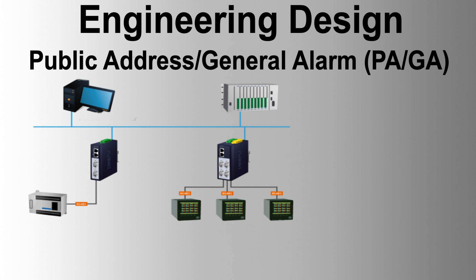System spare capacity and spares: 20% spare capacity on interface I/O cards, wired and terminated. 15% spares for cards, terminations, and slots available but not installed. 25% expansion space in cabinet racks. 30% maximum system memory utilization under maximum load for servers and workstations. 50% spare storage capacity memory for servers and workstations. 100% spare software license capacity. Spares are exclusive of commissioning and two-year spares supplied by the vendor.